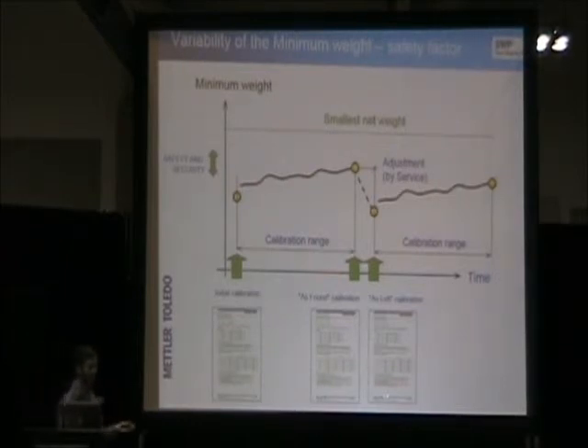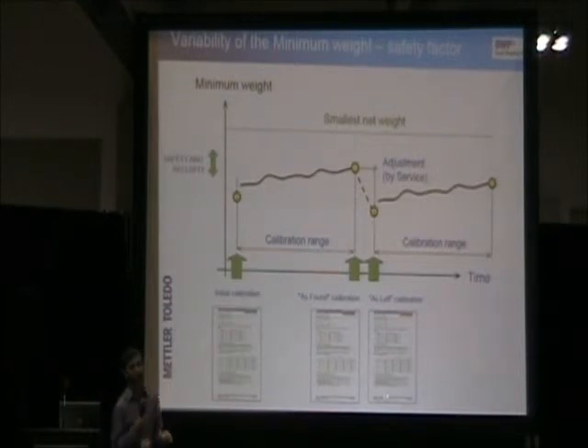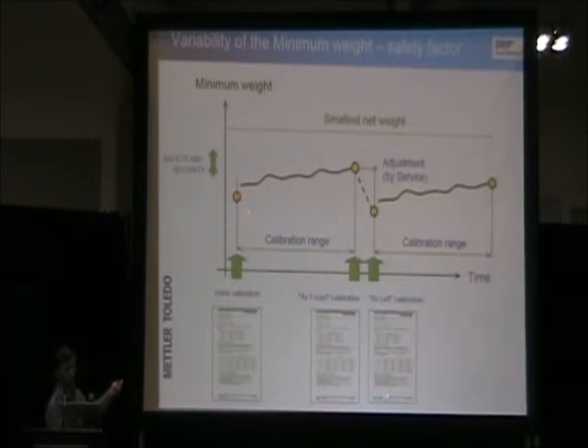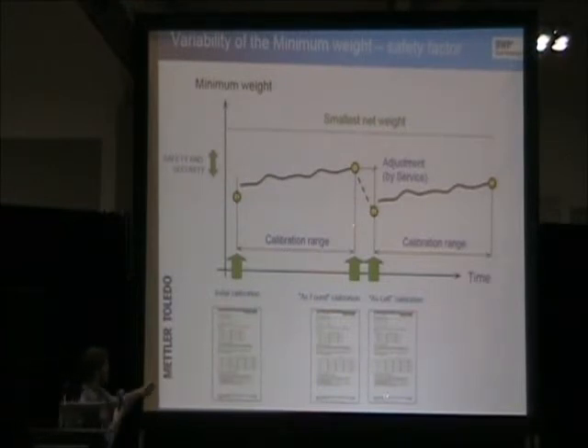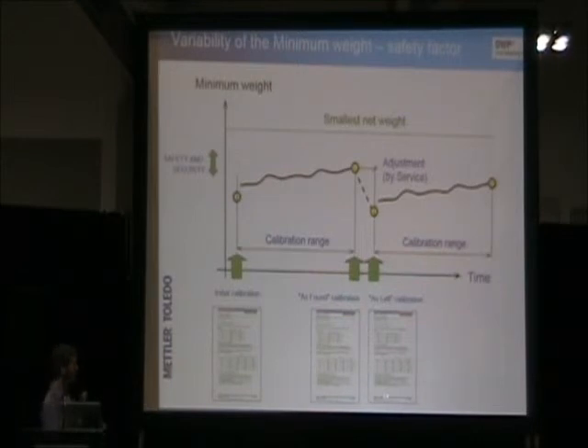Sometimes, in all honesty, it can actually decrease. But the point is that it's not going to stay the same. When you establish that minimum weight, when you do your initial qualification, operational qualification, when you first get that balance, it's not going to be the same throughout the entire year. So when a technician comes and tests the actual minimum weight, he might notice that it's higher than it was 6 months ago. So he'll readjust it, or as left, as it's called, back down to the value it was before. Again, once that technician leaves your facility and you start performing weighings on that particular instrument, your minimum weight is going to change.